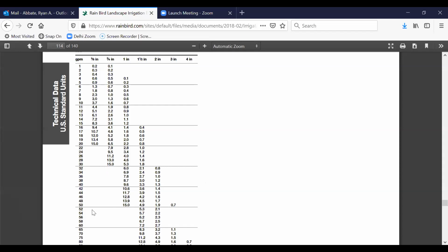We came up with that 50 by going to the 1-inch meter at the bottom of this chart; as much as we could push through this meter is 50 gallons per minute. However, we have to be at 75% of that safe flow, so we take 50 gallons per minute, multiply by 0.75, and get 37.5 gallons per minute that we can push through that meter safely.